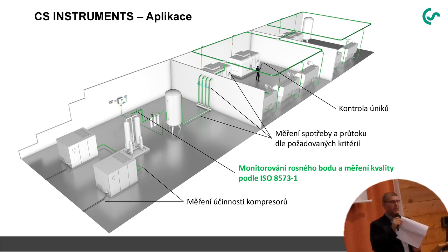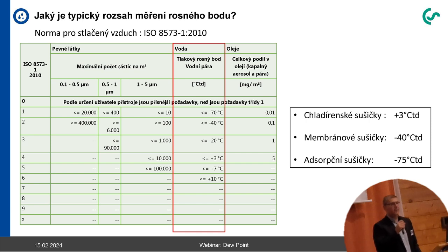Okay, so let's come to the next topic. The next topic is dew point monitoring and air quality measurement according to ISO 8573-1. One of the factors which should be measured is the so-called dew point. Compressed air should be dry. If you have compressed air which is wet, you will get a lot of problems. Therefore, there is an international ISO standard with certain limits. For example, if you have class 1, your dew point should be below -70. If you have class 2, the dew point should be below -40, and so on.